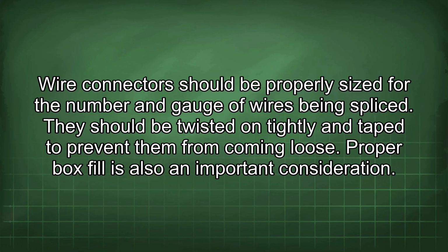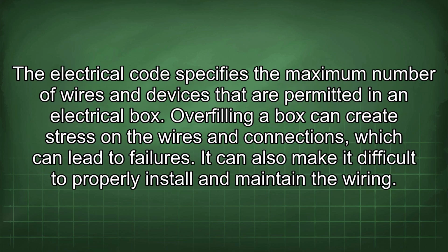from coming loose. Proper box fill is also an important consideration. The electrical code specifies the maximum number of wires and devices that are permitted in an electrical box. Overfilling a box can create stress on wires and connections, which can lead to failures. It can also make it difficult to properly install and maintain the wiring.